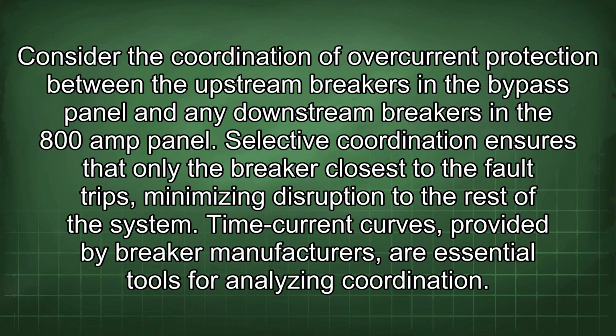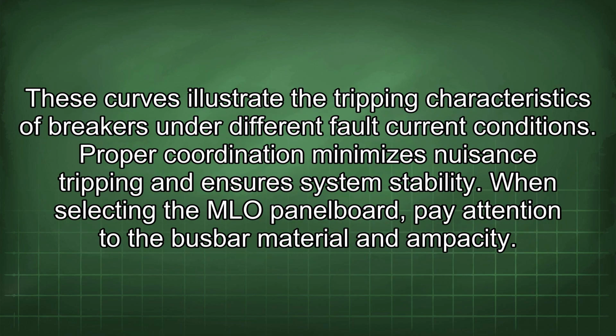Consider the coordination of overcurrent protection between the upstream breakers in the bypass panel and any downstream breakers in the 800 amp panel. Selective coordination ensures that only the breaker closest to the fault trips, minimizing disruption to the rest of the system. Time current curves, provided by breaker manufacturers, are essential tools for analyzing coordination. These curves illustrate the tripping characteristics of breakers under different fault current conditions. Proper coordination minimizes nuisance tripping and ensures system stability.